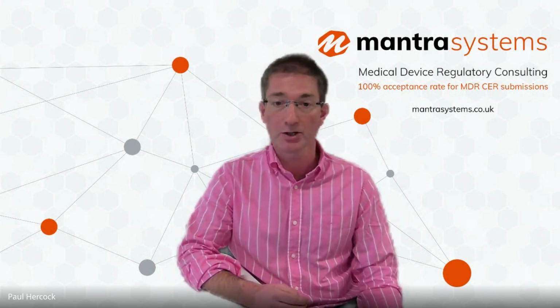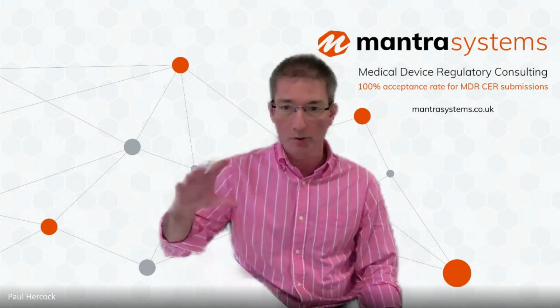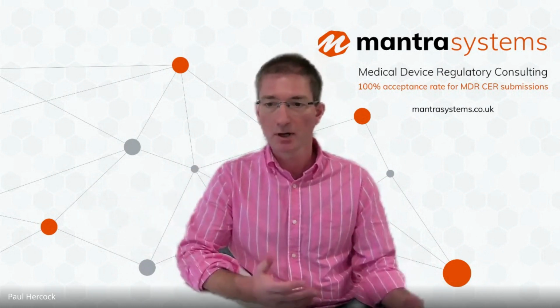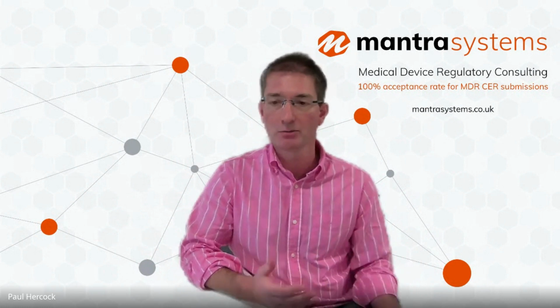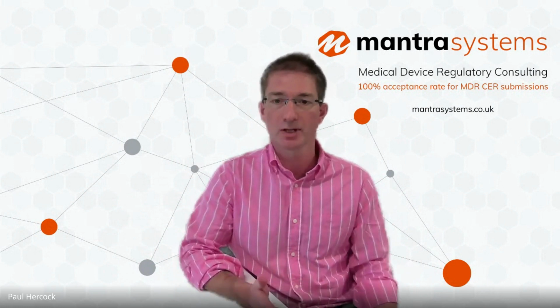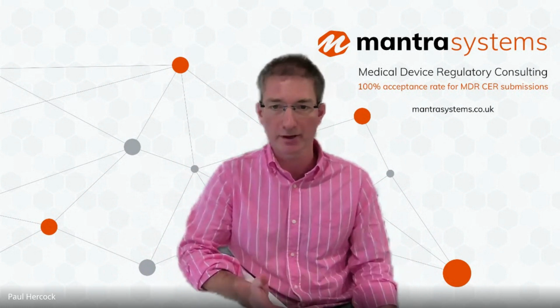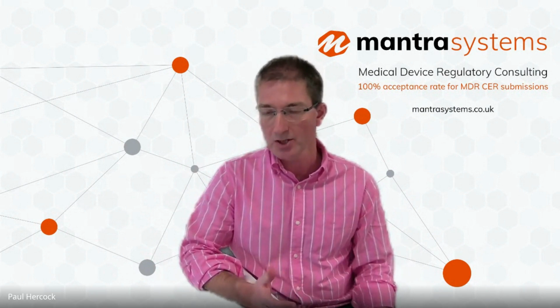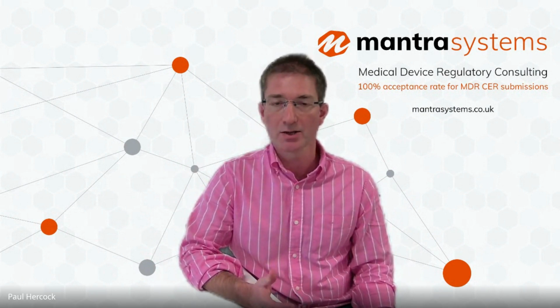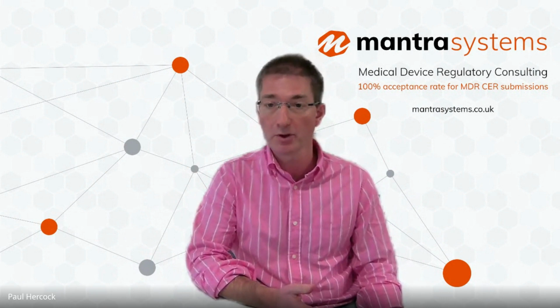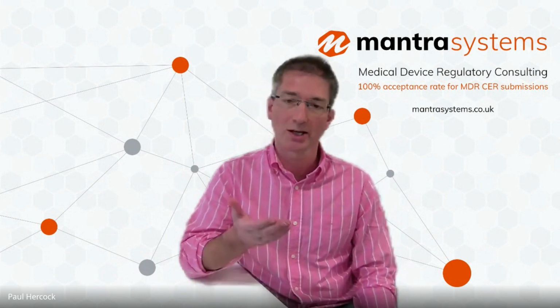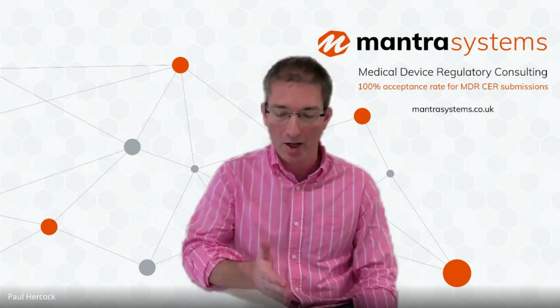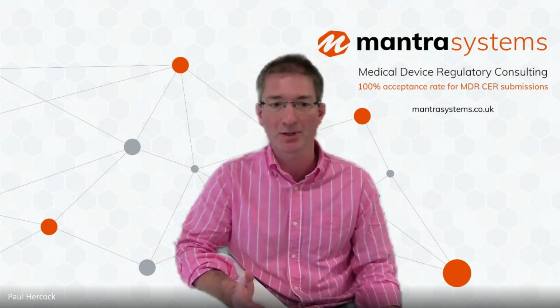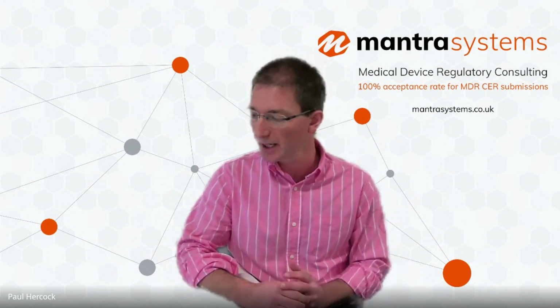So if you manufacture an oxygen pipe or gas tap or something, there's no way you can generate clinical evidence on that because it wouldn't relate to its function. Its function is entirely technical, it's delivery of a gas. So Article 61(10) is designed to allow another route to conformity for products like that. The key test is that clinical evidence is inappropriate, not that it's not available. So it's not a get-out for an absence of clinical data.